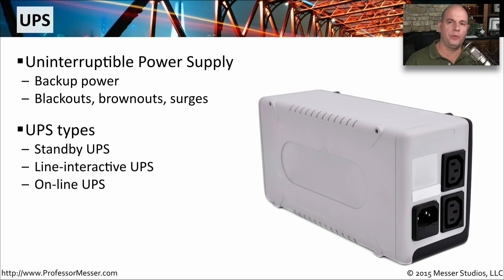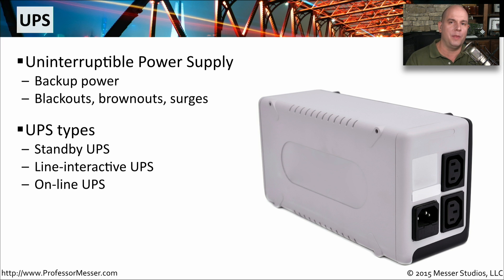You'll generally have three different kinds of UPSs to choose from. The first is the standby UPS. With the standby UPS, the UPS is not operating at all, and if power is lost, it recognizes there's no more power and the batteries then kick in. So there's a time delay between the time when you lose power and the time that power is being provided by the battery.